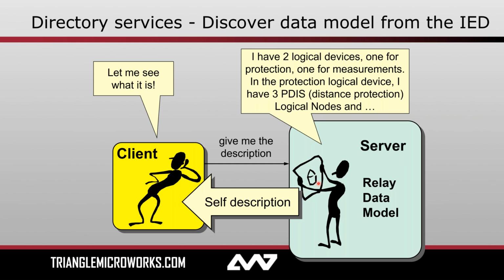So in this example, the server is saying, hey, I've got two logical devices. This goes back to that hierarchy that we discussed in webinar 2. One is used for protection, one for measurement, and then I have a series of logical nodes, data objects, and data attributes on each one. All of that information can be passed up to the client, and more. We can learn about what report control blocks that device is capable of sending, what GOOSE messages it's capable of publishing, and so on and so forth. So this has two applications. The more basic one would be for the client to go out, learn about the server, and then decide what information it wants to request or read, or what reports it wants to enable.